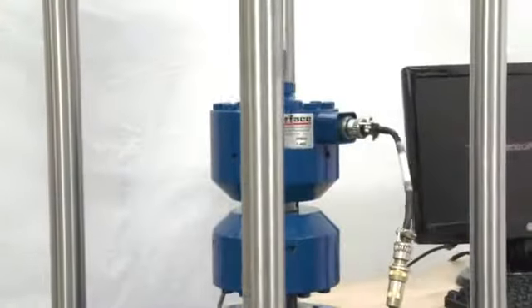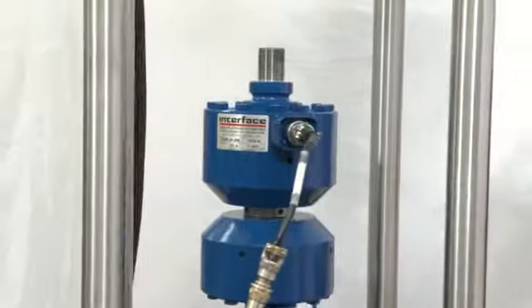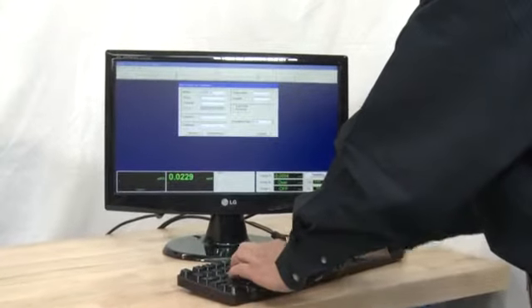Interface has packaged its expertise from the calibration of tens of thousands of load cells into a user-friendly system where high accuracy calibrations can be conducted with minimal training. Pull-down menus and step-by-step instructions guide the operator through a complete load cell calibration.